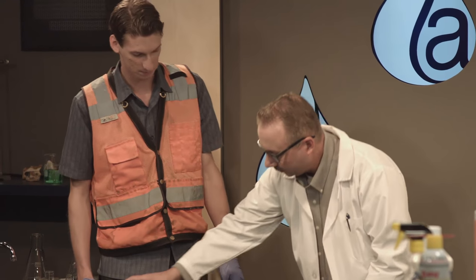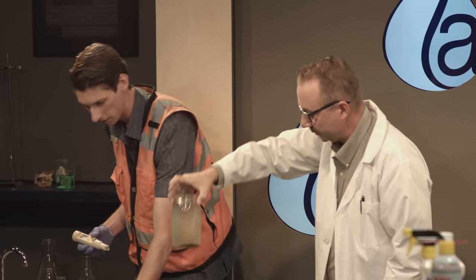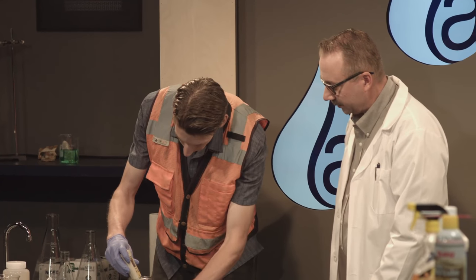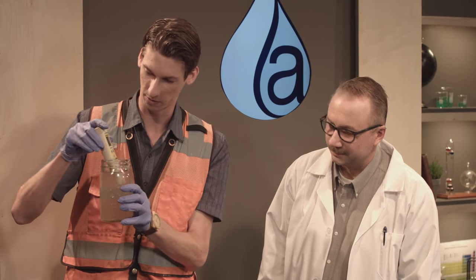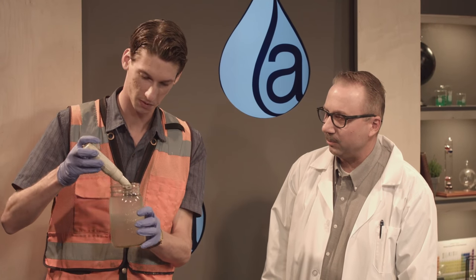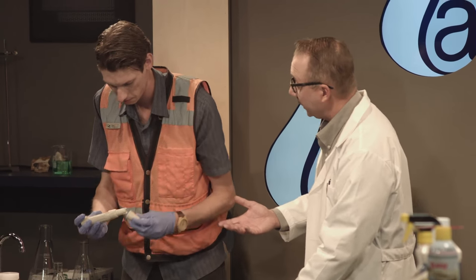We got 82.3. So that's actually within the limits — well below 250. We're going to take a pH sample of that too. It's jumping up to over 10 now. So that's concerning. That would be indicative of some pH-altering influences from maybe concrete, lime treatment, mortars — a lot of different things. We don't want to just look at our sampling point; we need to see what activities were happening upstream of that.